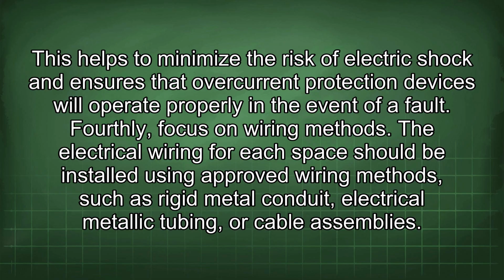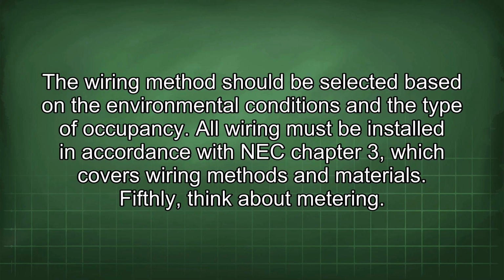Fourthly, focus on wiring methods. The electrical wiring for each space should be installed using approved wiring methods, such as rigid metal conduit, electrical metallic tubing, or cable assemblies. The wiring method should be selected based on the environmental conditions and the type of occupancy. All wiring must be installed in accordance with NEC Chapter 3, which covers wiring methods and materials.